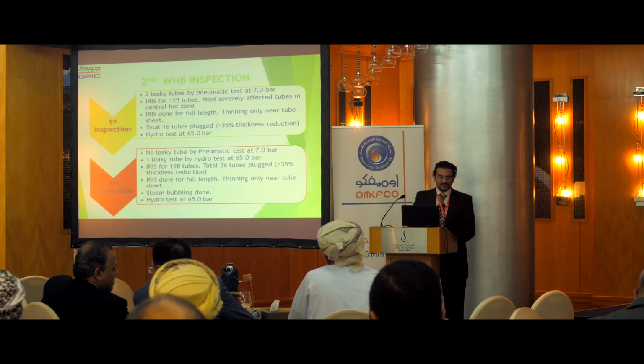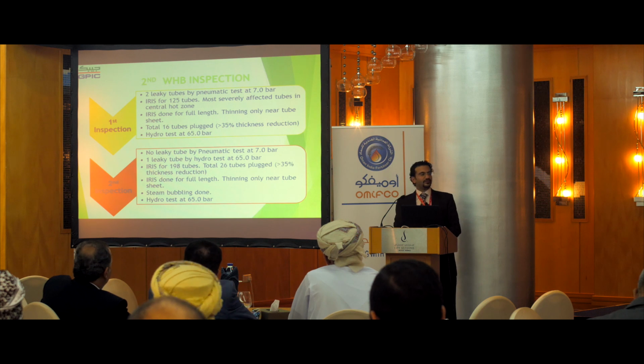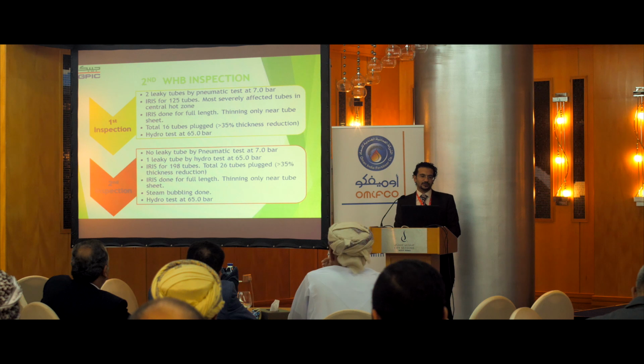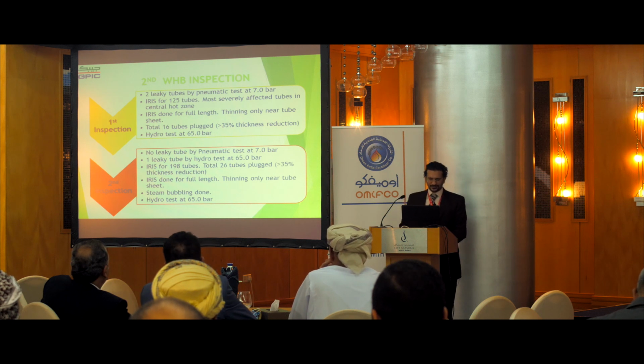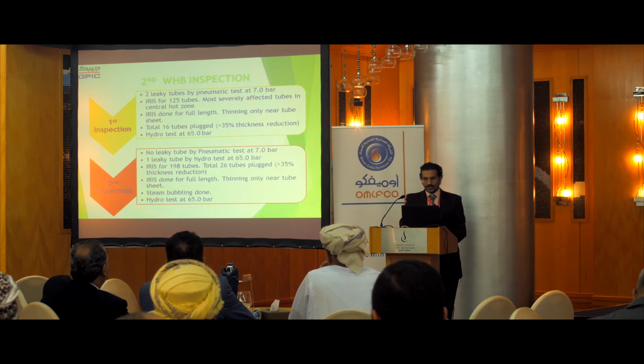Our second waste heat boiler went through several inspections after the leaks. So 2 leaky tubes were found the first time it was inspected, and a total of 16 tubes were plugged. Hydro tested at 65 bar later on, it was found okay.